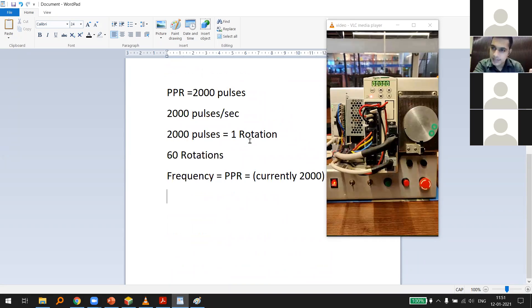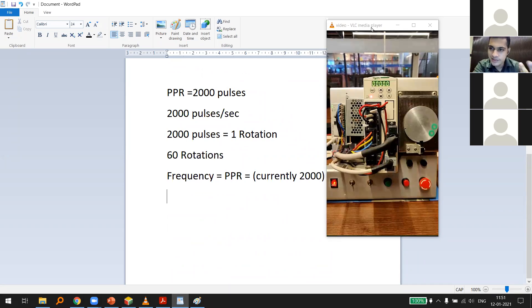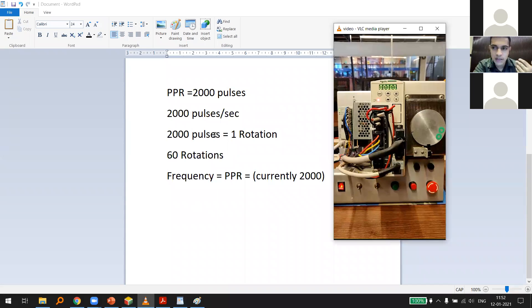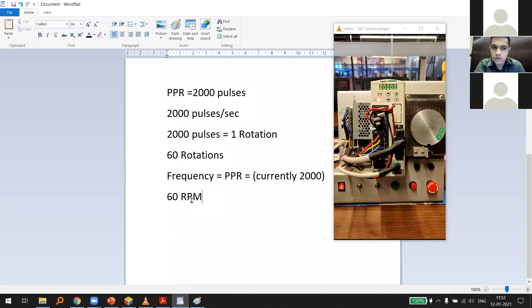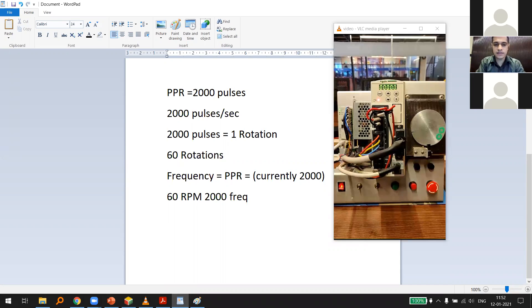If frequency equals PPR (currently 2,000), rotations per second is 1, which is 60 RPM. So giving a frequency of 2,000 pulses per second produces 60 RPM output. For a visible demo, instead of 60 RPM let's give 6 RPM by setting frequency to 200, which is 2,000 divided by 10.